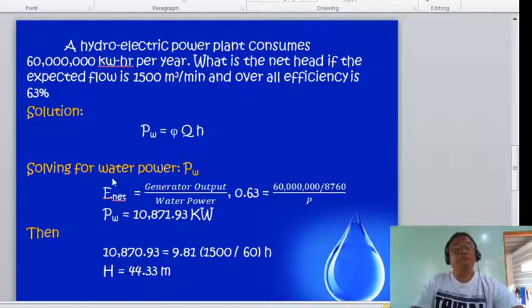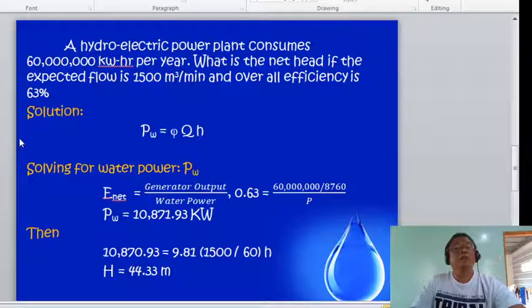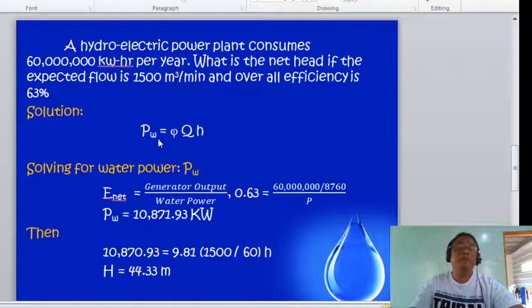Getting the head: efficiency of 0.63 equals generator output divided by water power. So 0.63 equals 60 million divided by 8760, which is the number of hours per year, divided by the water power. Water power now is 10,871.93 kilowatts.